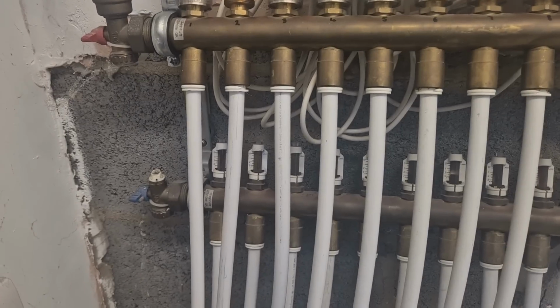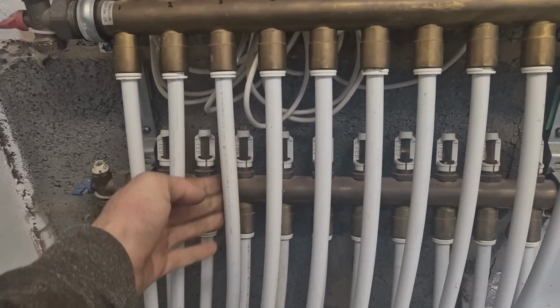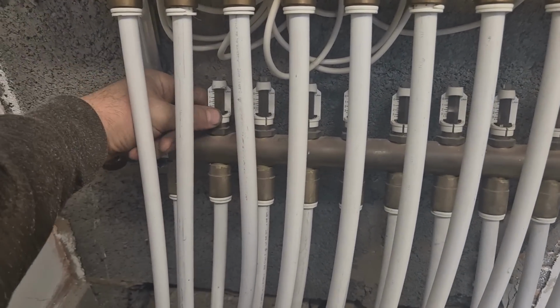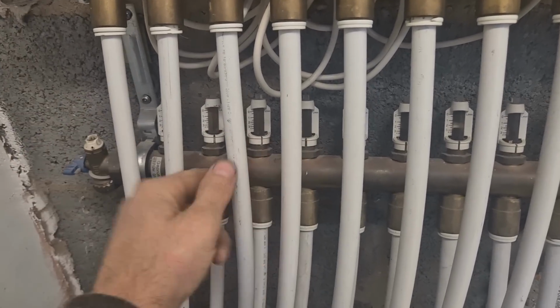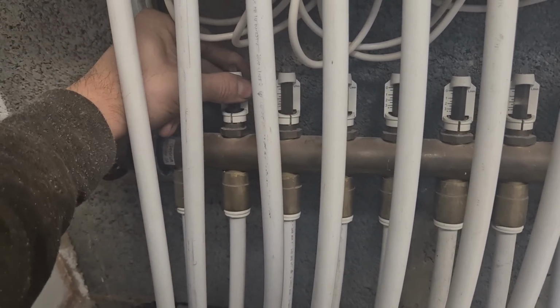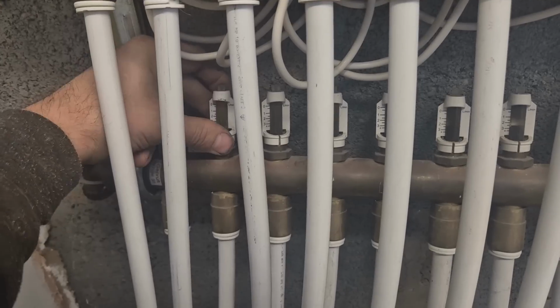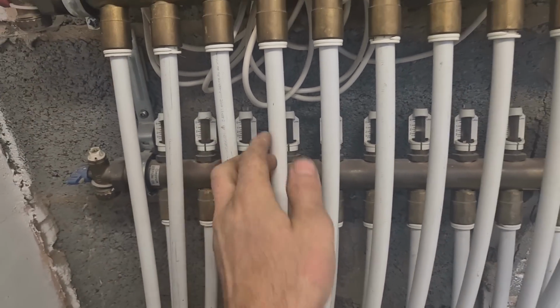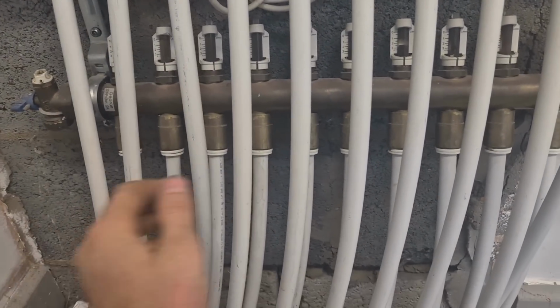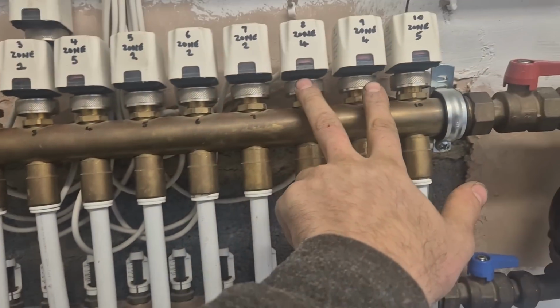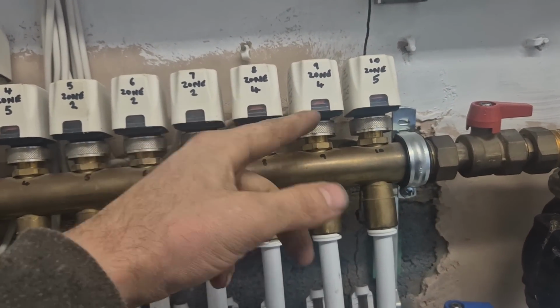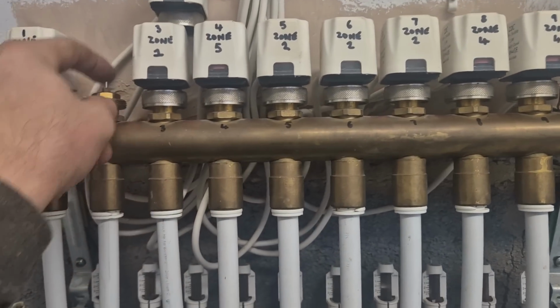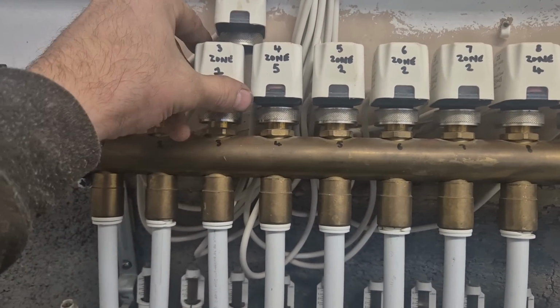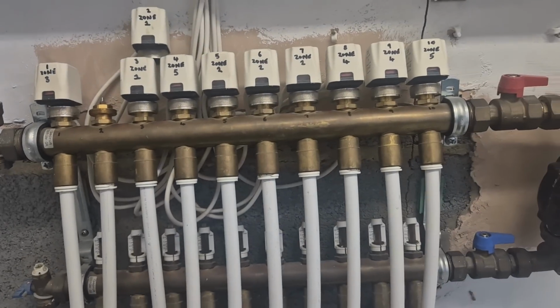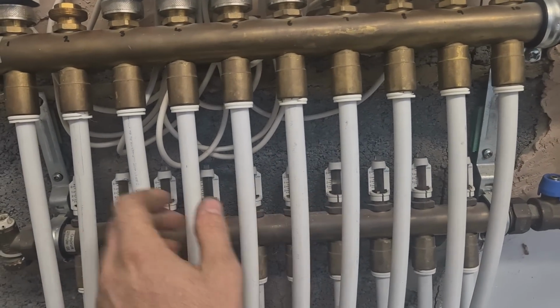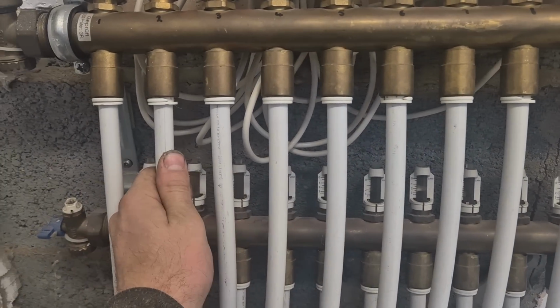But there's a stupid way of piping this, because normally you take them behind so you can get to these. That one doesn't appear to be letting any water through, but I don't know if it's just stuck, so I'm going to try and clean that out. I think that should just pop off. But yeah, I don't know why they've done it like that, because it makes it hard work to work on. Them aren't calling, because you can see by the little red indicators. But I think zone 1, only half of it's getting hot, but they haven't even left a chart to show you which room's which. I think this one here is the problem loop.